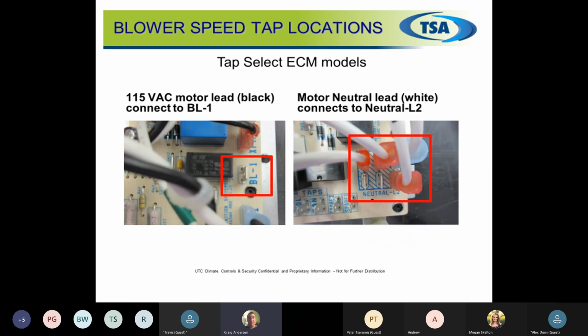So here's what your 115 volt taps will look like. They'll all be pretty much the same on all boards. You're going to have your neutral spot, where all your neutrals from your blower motor, your door switch, and incoming power are usually ganged up on your board. And then your power going to your fan motor is usually tagged BL1. So that's going to be 110 volts coming out of your boards to your motors at all times.